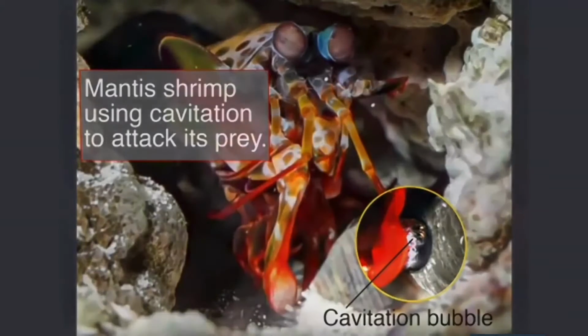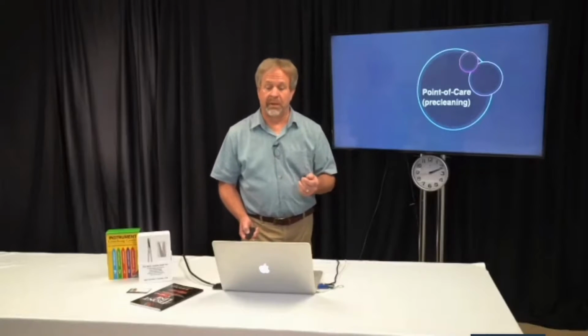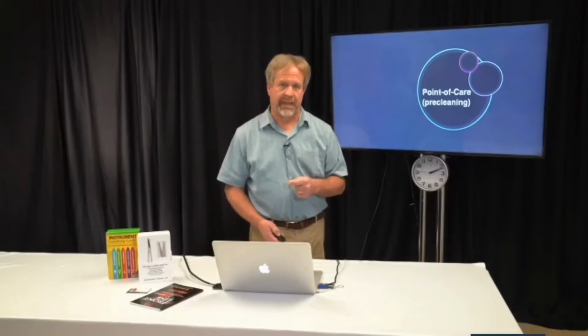It has this appendage, like a praying mantis, and it attacks its prey by beating up on a shell and creating a cavitation bubble like you see here, where actually a high temperature can emanate, but the real effect is happening because the cavitation bubble is creating that implosive effect that allows it to catch its prey. So you really understand a little bit better now about cavitation and perhaps gained a better appreciation of that power that you use every day and perhaps take for granted. But ultrasonic cleaning is only as good as the time and effort you take to make it right, to do it well. Let's talk about point of care cleaning just a little bit. Now, it used to be point of use cleaning, and AAMI has now adopted the point of care terminology.